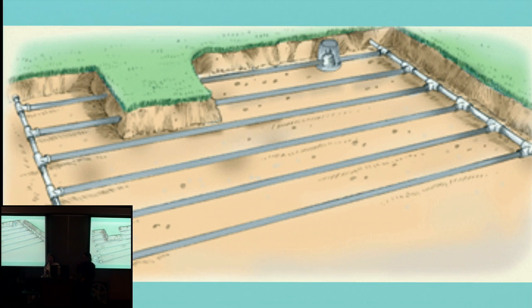There are a couple of different flush valves that we use, automatic flush valves or ball valves. With the automatic flush valves, I just have them open the box up for me when they turn the valve on. We just want to make sure that there's a flush when the system comes on, and that it goes off when the system is fully charged. If it doesn't go off, then the flush valve's leaking and they need to replace that. If they're using a ball valve for a flush valve, then you just want to have them open that ball valve up. Just make sure the water's flowing out of there without any restriction.